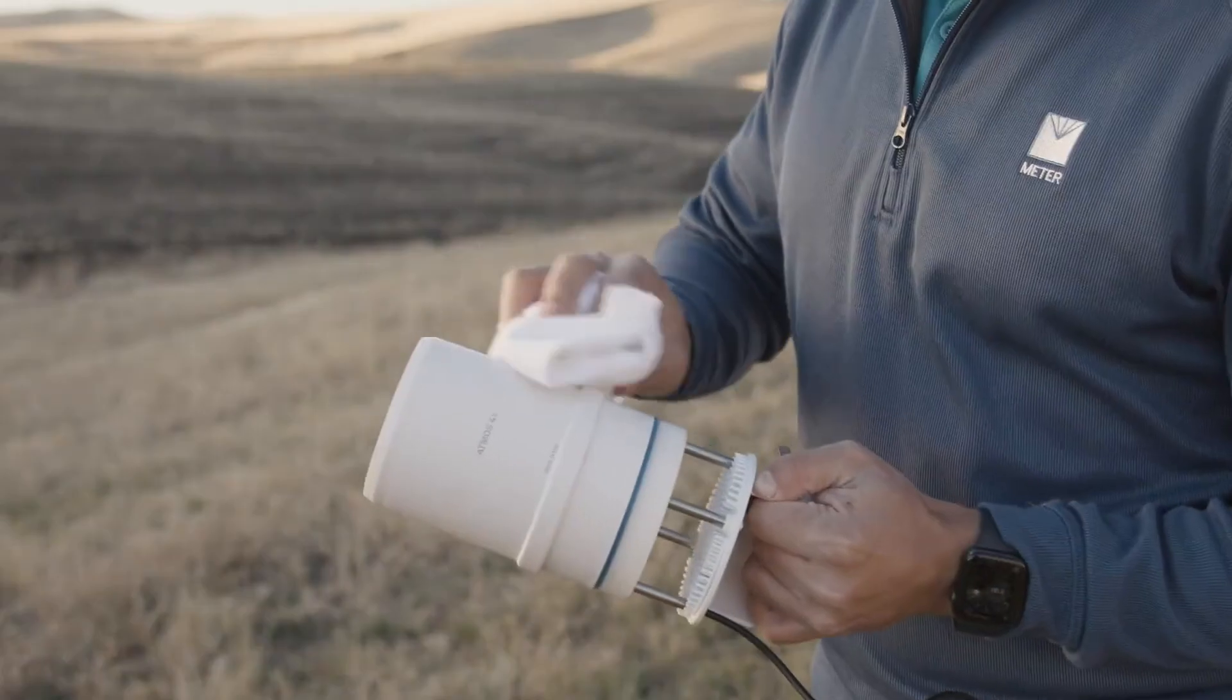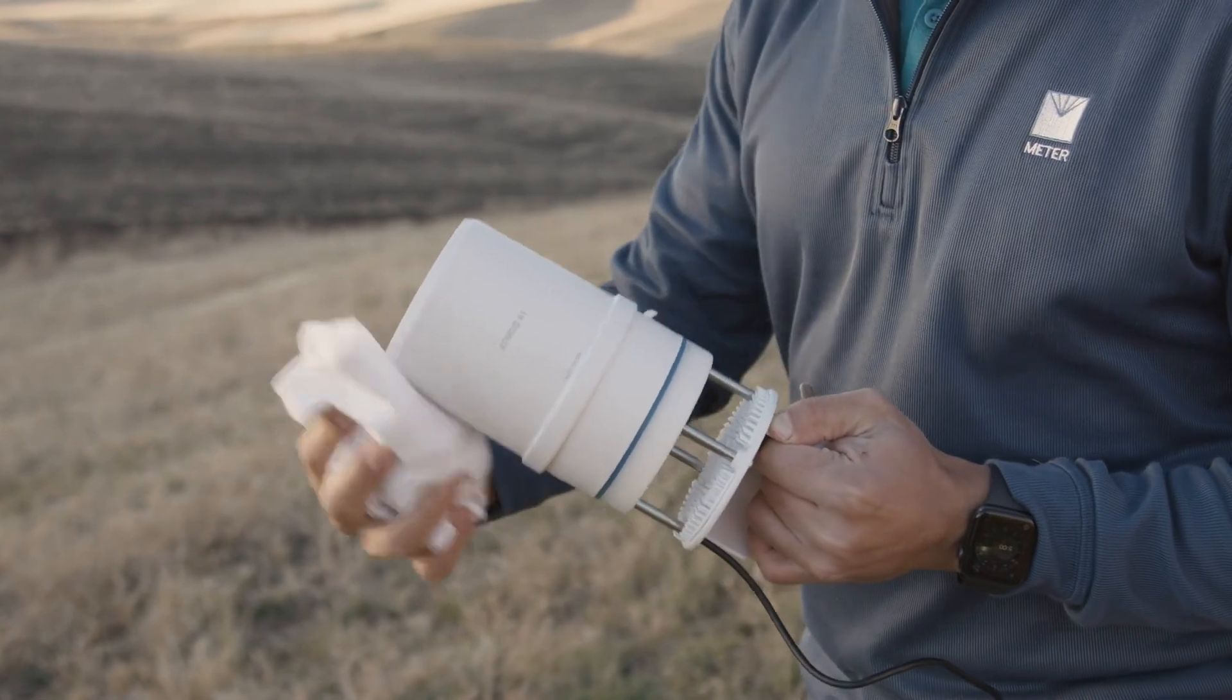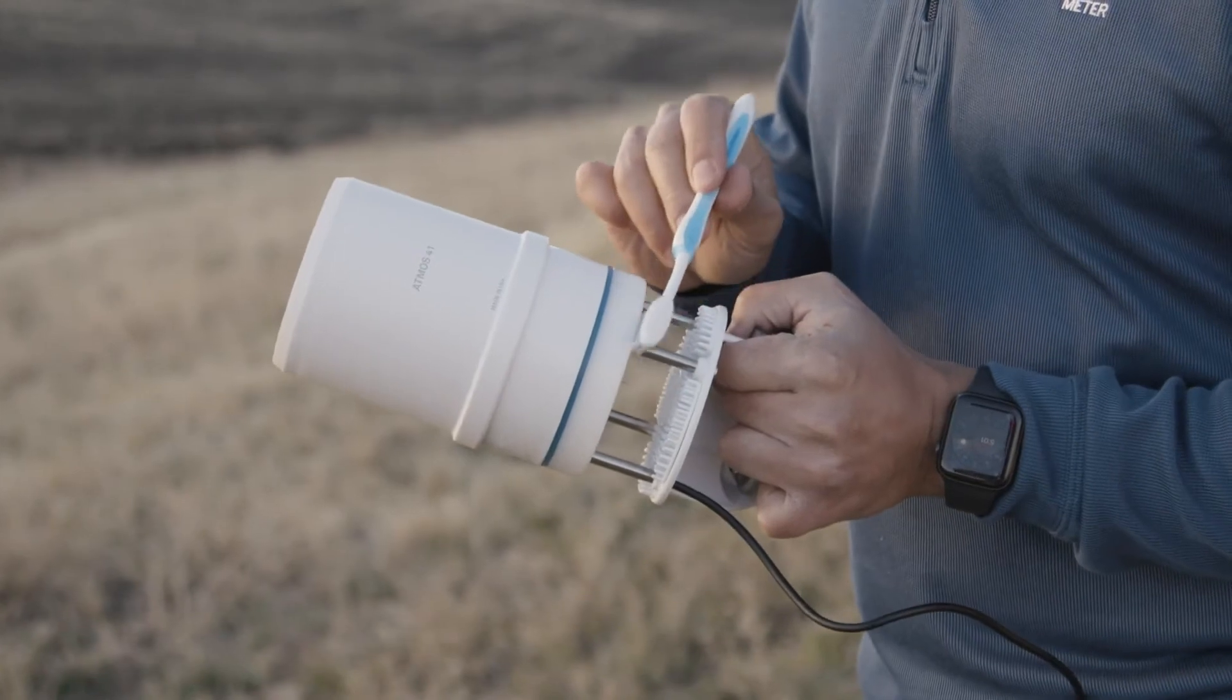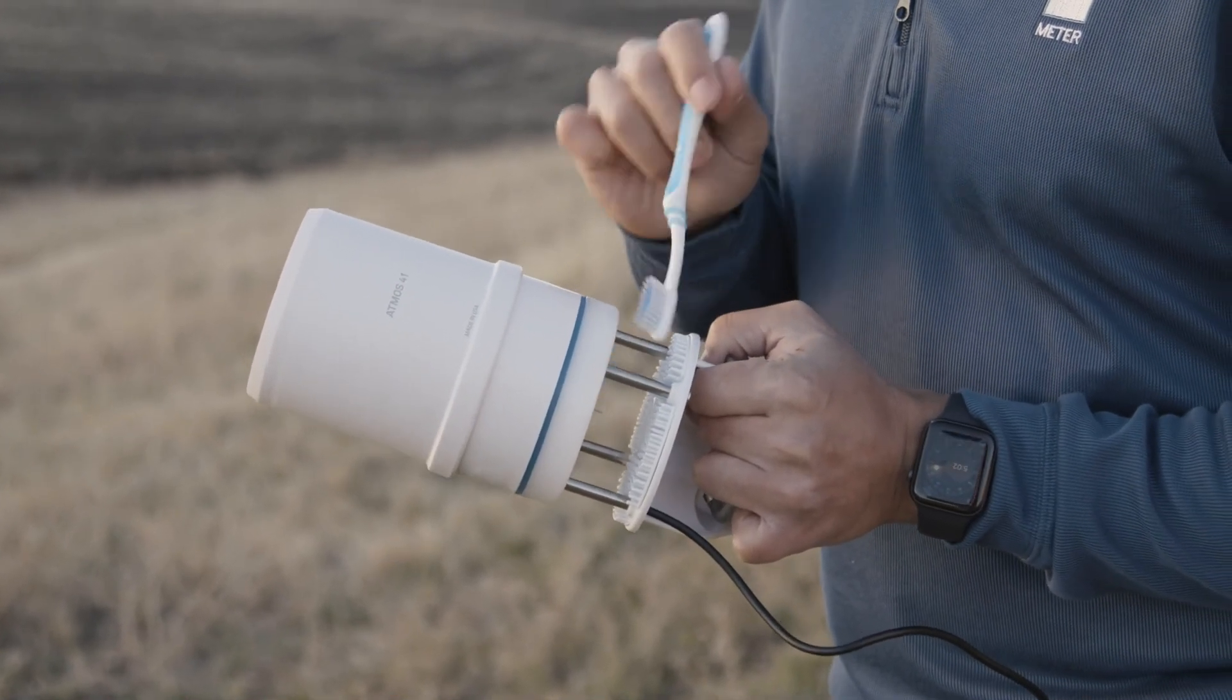To clean the Atmos 41 body, scrub the Atmos 41 body with light to medium pressure using a damp cloth. A warm damp cloth is best. Do not immerse the sensor suite in water. Clean around posts and between crevices using a dry brush.